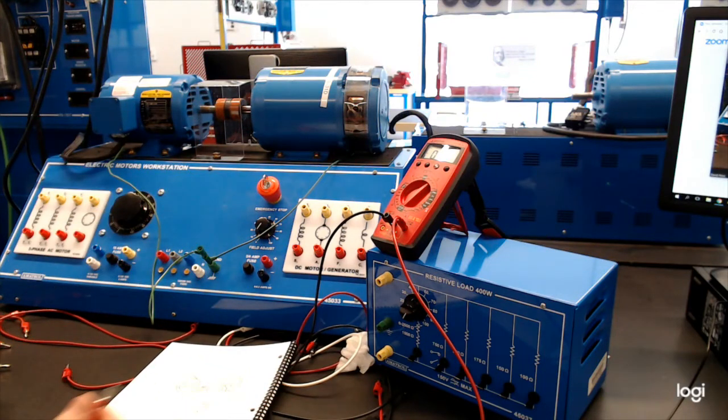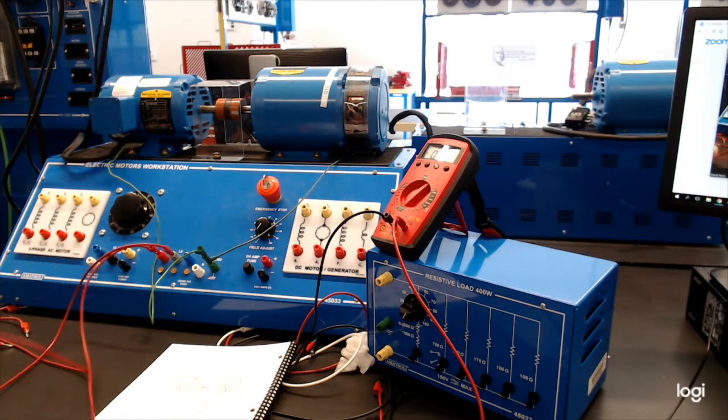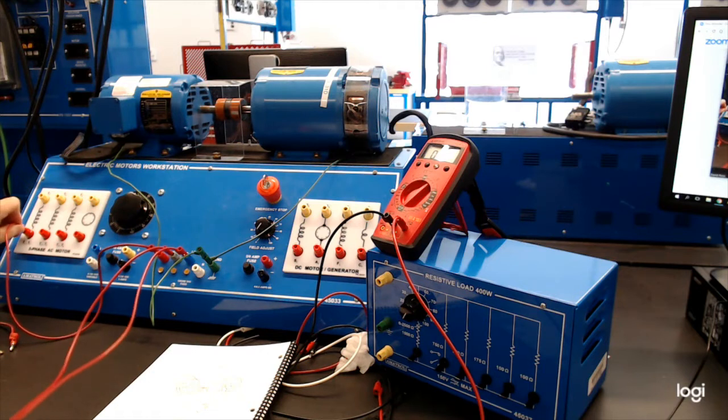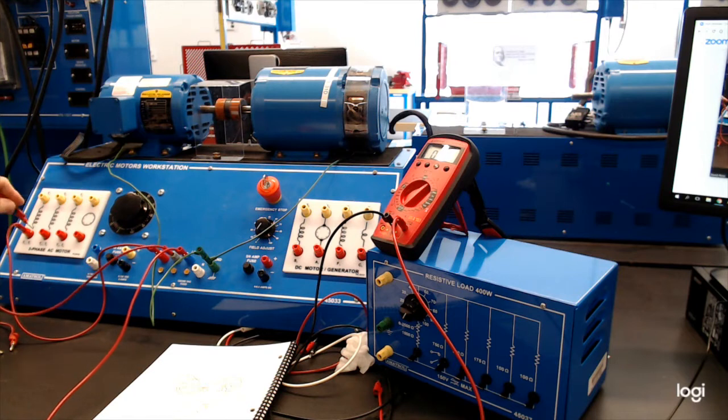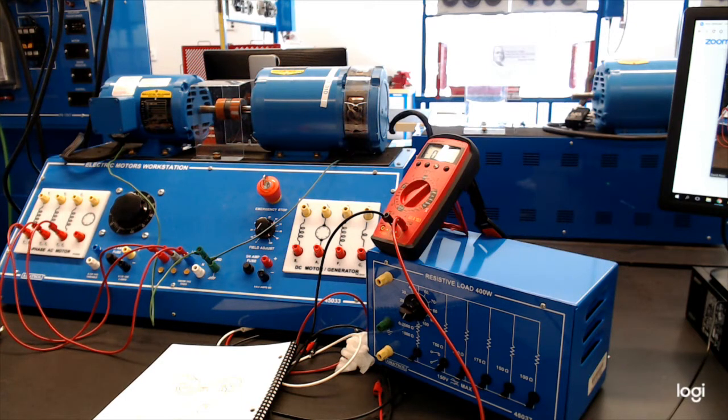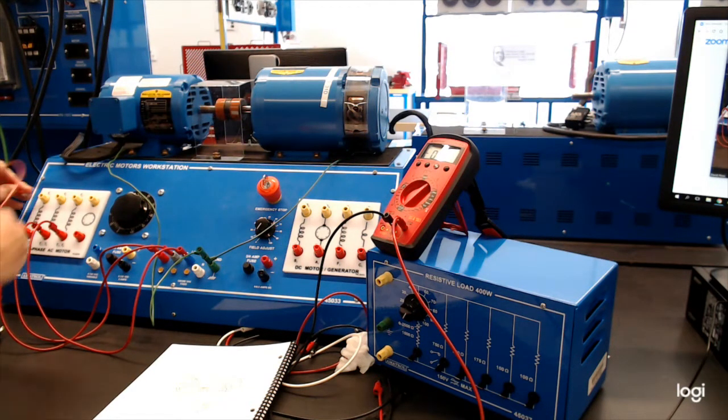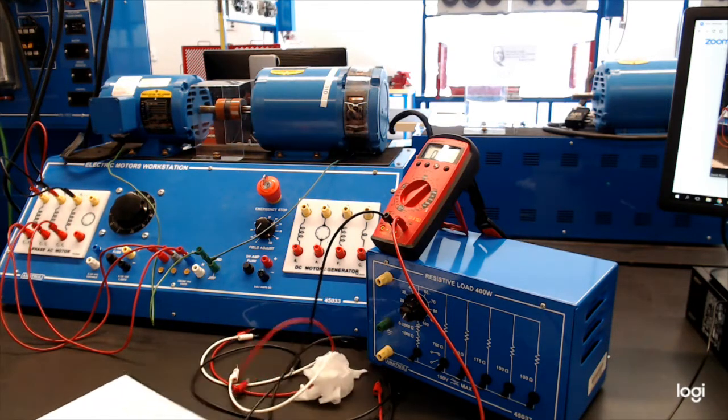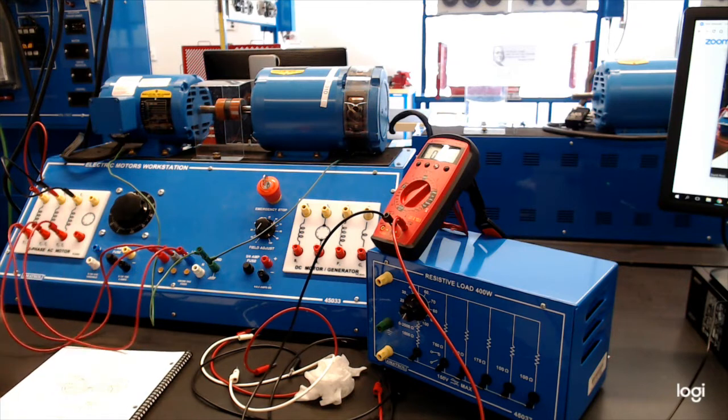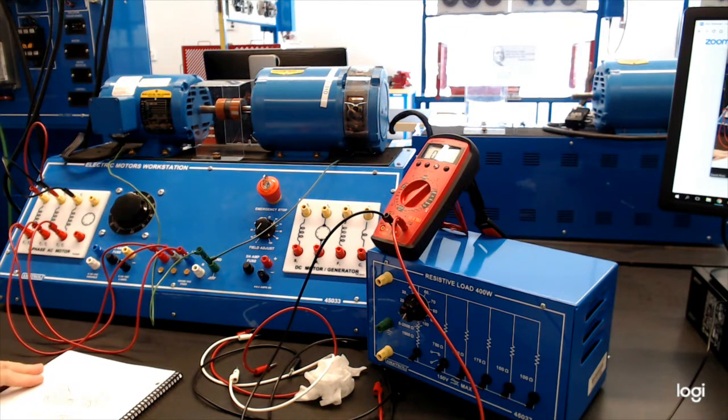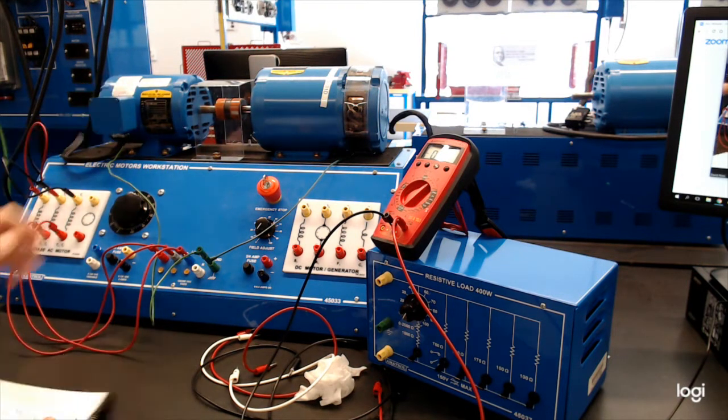Now, we will know, and we'll get real familiar with this soon enough, but for a three-phase motor, we're going to bring in three-phase power to this motor. And we'll discover that there's something called a wye connection and something called a delta connection. We actually have wye configuration in our lab. So just for the time being, we'll just leave it at that. And so we're wiring up a three-phase motor in a wye configuration, and we'll go into all the particulars about that later. We'll discover that there are actually nine leads, and sometimes we're putting the windings in series, and sometimes we're putting them in parallel. For Y configuration, we're actually putting the winding halves in parallel. So this motor is good to go. It's connected and ready to operate as a three-phase AC induction motor.